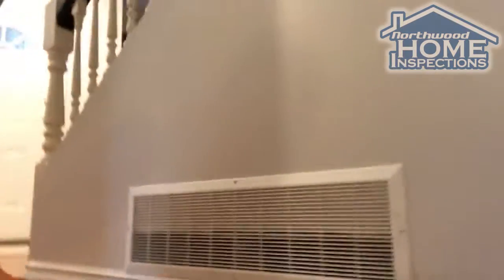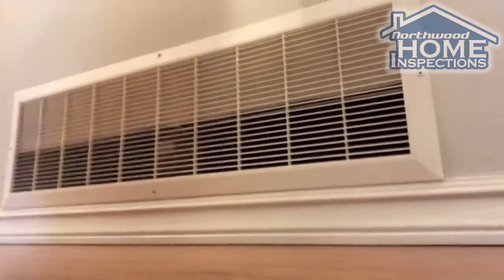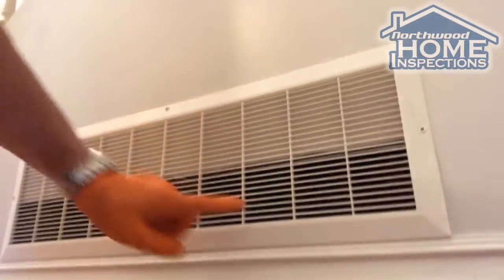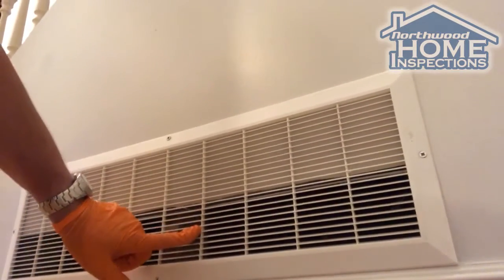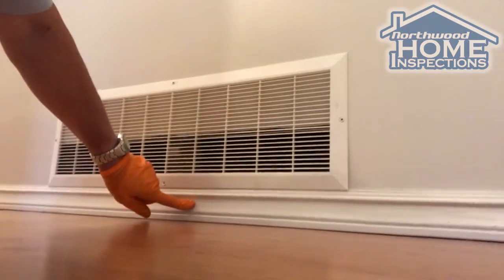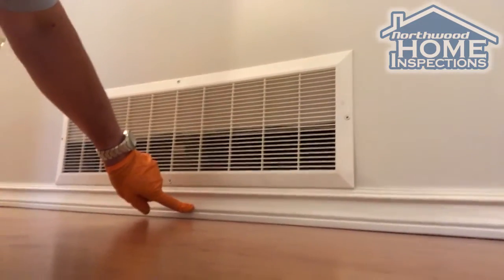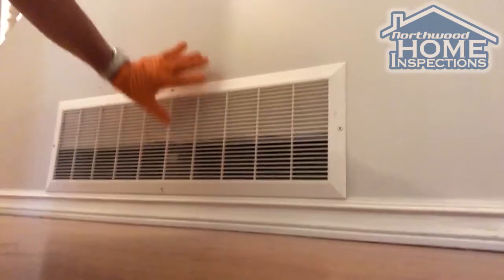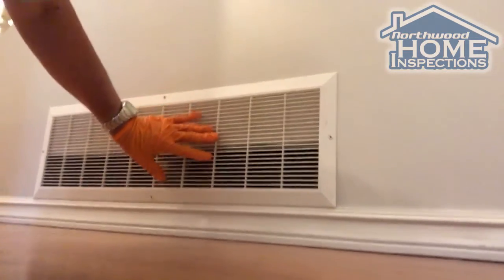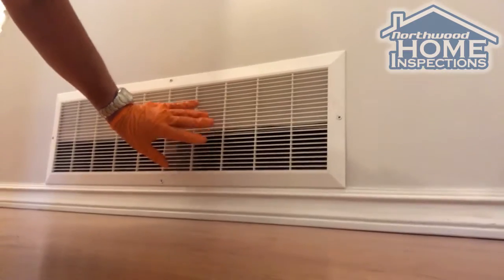You can see this is drywall behind here, and this is the vent opening for the return air. The problem — I'm willing to bet — is that this house was originally built with no baseboard, and when somebody installed the baseboard they ended up covering that return air grille without even thinking about return air getting into the return air plenum and then to the furnace.